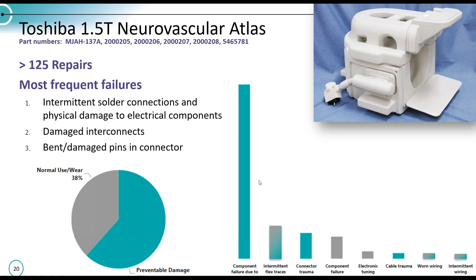Again, an oddly shaped coil that is cumbersome in nature. It can take a quick tumble to the floor. And also, the third type of failure is just bent, damaged pins in the connector. So by far, component failures due to trauma is the number one type of failure with this type of probe or the coil.